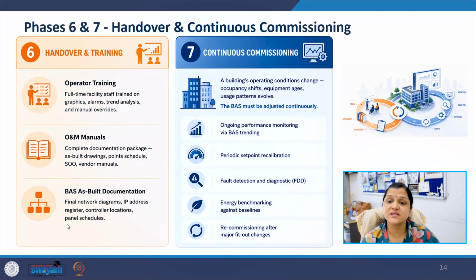However, the BAS life cycle does not end here. Continuous commissioning is extremely important. Building conditions constantly evolve. Occupancy changes, equipment ages, and interior layouts may change. Therefore, building automation system settings must be recalibrated periodically. Continuous monitoring, fault detection, diagnostics, and energy benchmarking help maintain long-term performance.